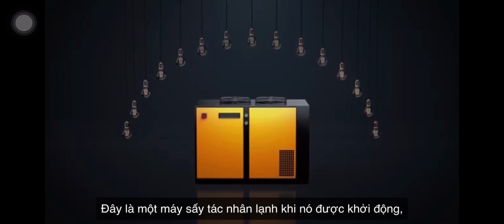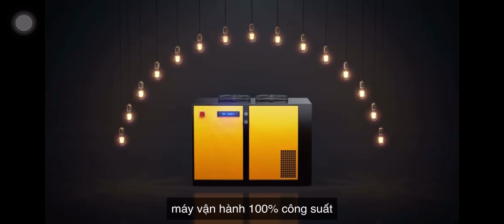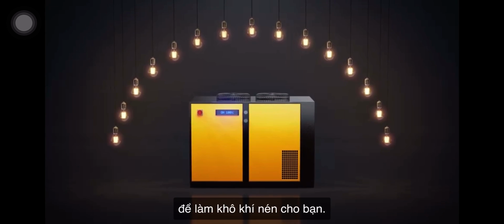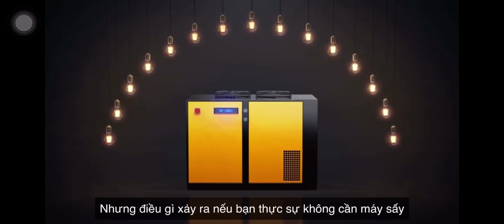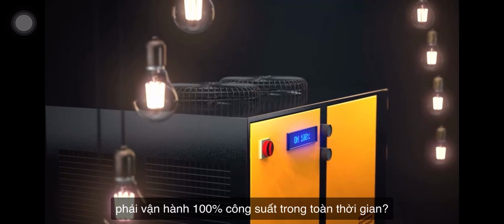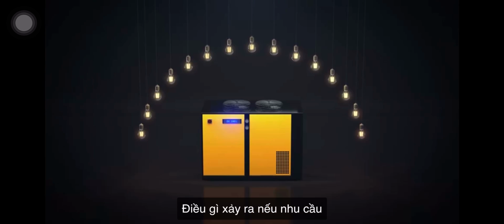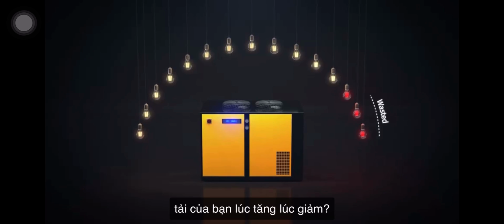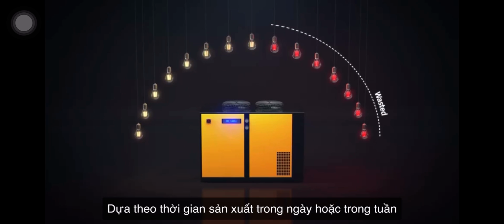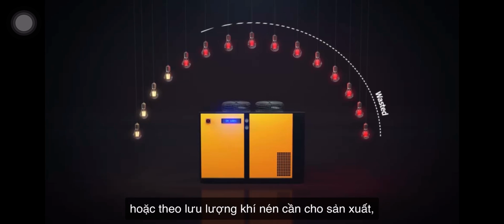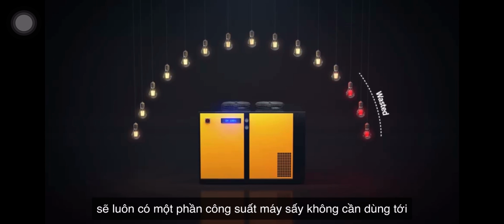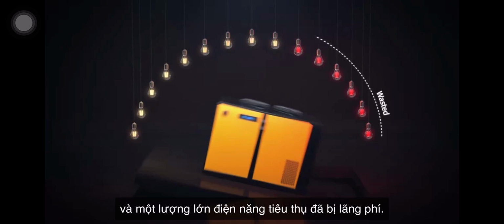This is a refrigerant dryer. When it is on, it is 100% on, working at full capacity to dry your compressed air. But what if you don't need it to work at 100% all the time? What happens if your need for compressed air goes up and down depending on the time of day or week or the flow of your production? What happens is unused dryer capacity and a whole lot of energy wasted.